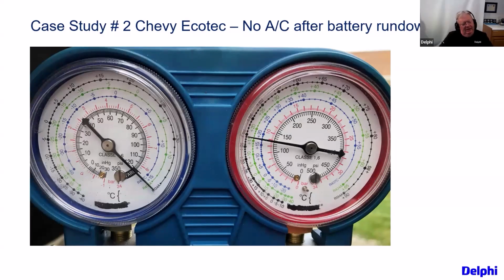So 1 degree is - until we get into the higher realm of pressure, that's when it kind of separates - 1 degree Fahrenheit to 1 PSI. That's why I guess there's still some silver lining to the cloud of Americans, including Puerto Ricans, being behind the times with the metric system. Because with the metric system, 1 PSI - they don't use that term, they don't use 1 degree Fahrenheit. So this relationship is handy for techs: 1 PSI, 1 degree Fahrenheit. That relationship goes out the window with kilopascals and Celsius.